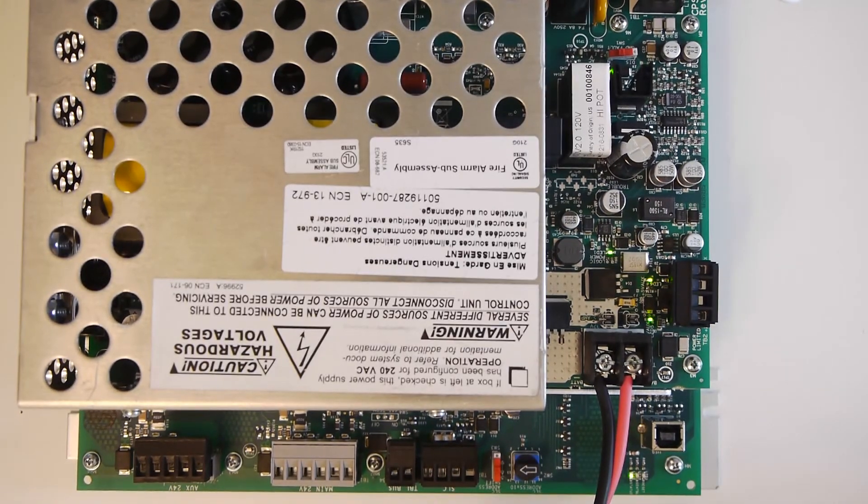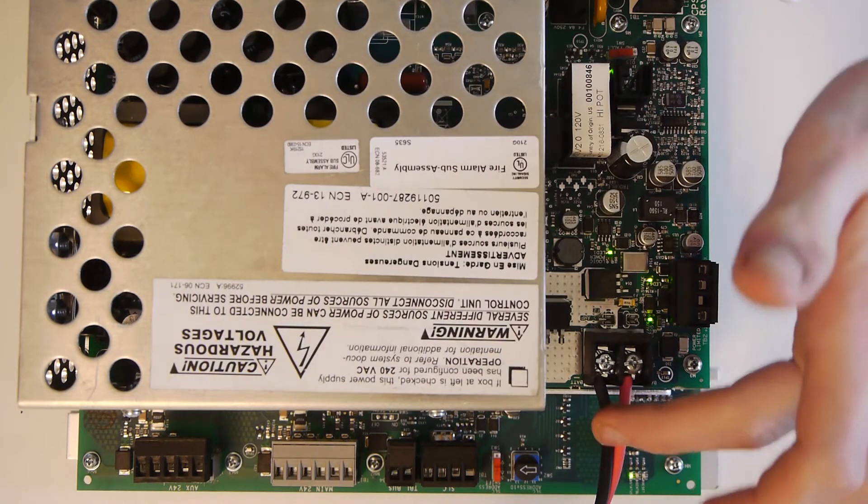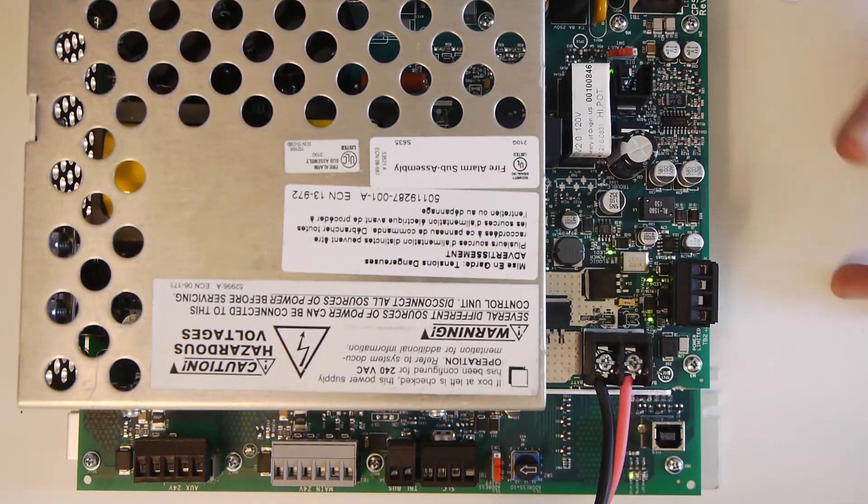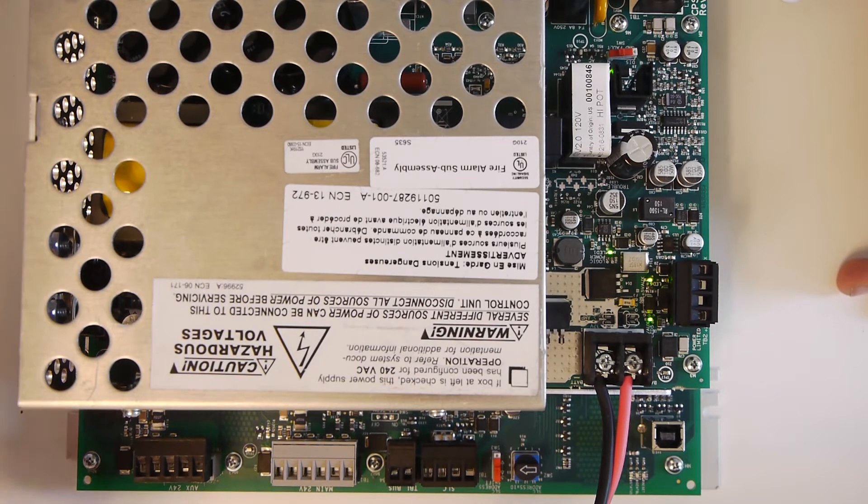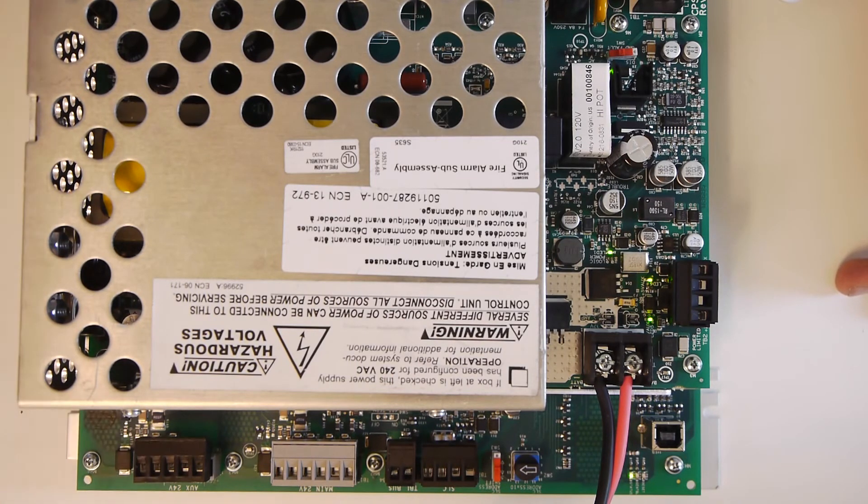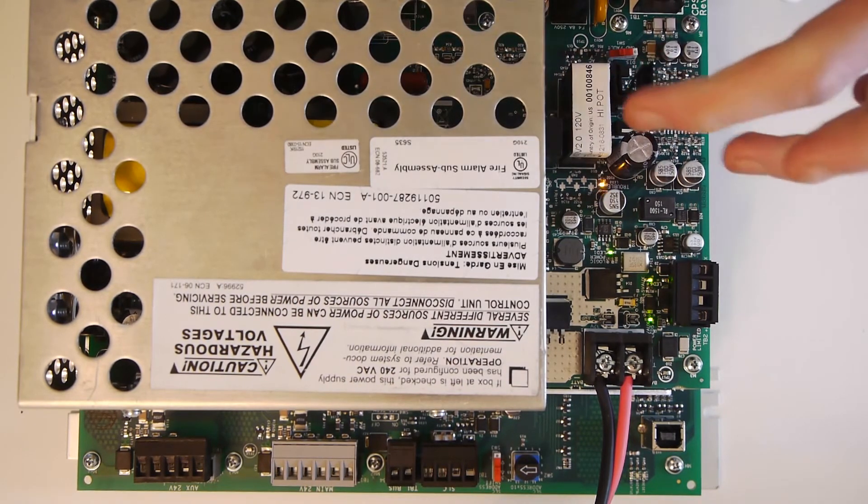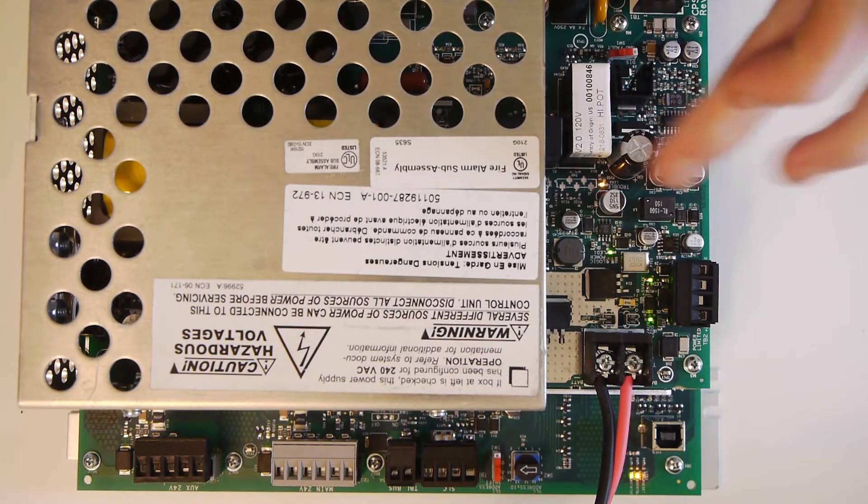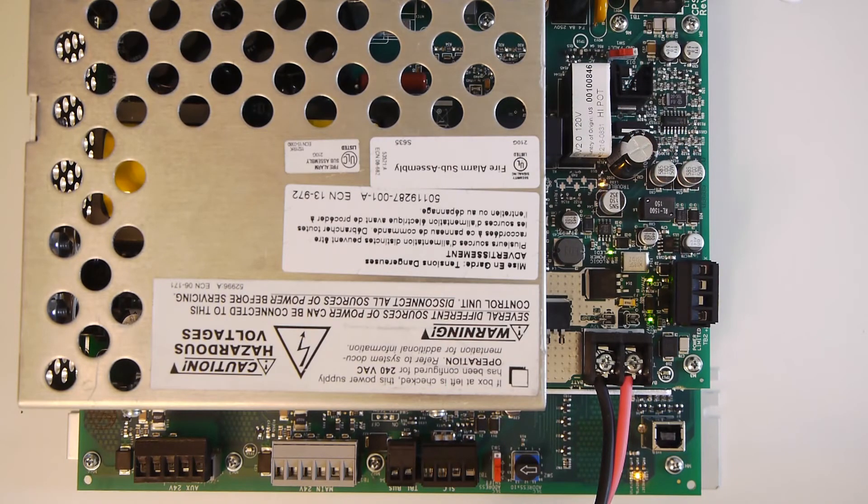So this power supply can be used by itself. If you plug in batteries and AC power without programming it, it will just work. You'll have 24-volt output. If you unplug the AC power like that, you'll see that you get a flash code on here, which if you look that up in the manual, that means low AC.